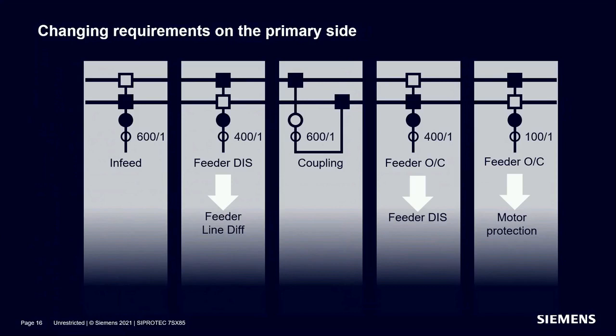Drag and drop the line differential functionality from the library into the configuration. Add the communications module to the hardware and the new functionality is available. No replacement of the device, no new wiring, only a change in the configuration. Both functions, distance protection and line differential protection, are using the same amount of function points. Therefore, there will be no additional costs. Alternatively, you can simply add the line differential and keep the distance protection as a backup.